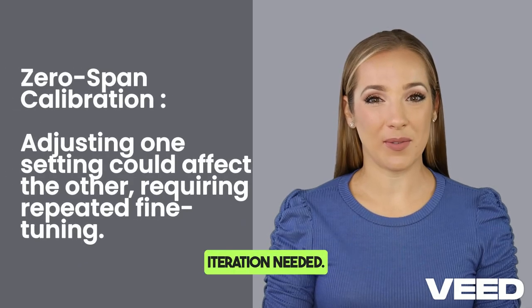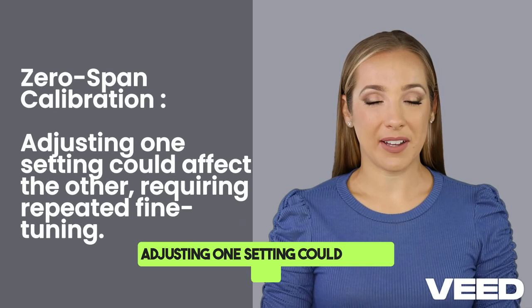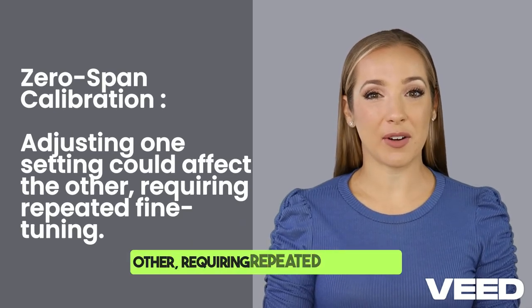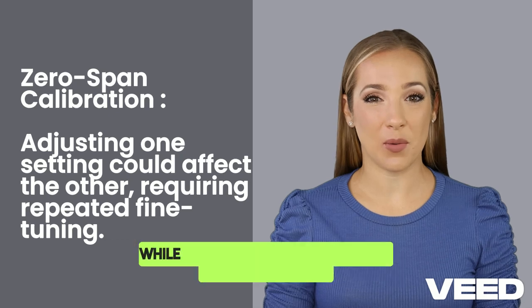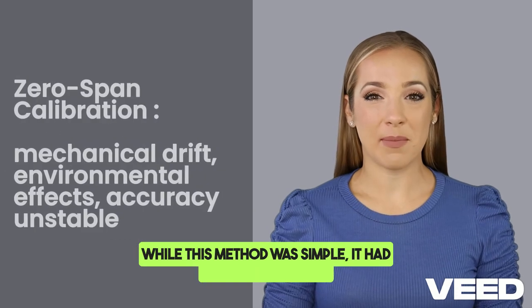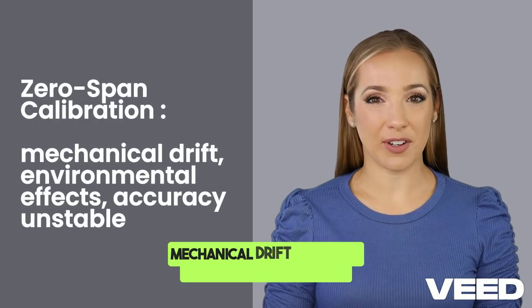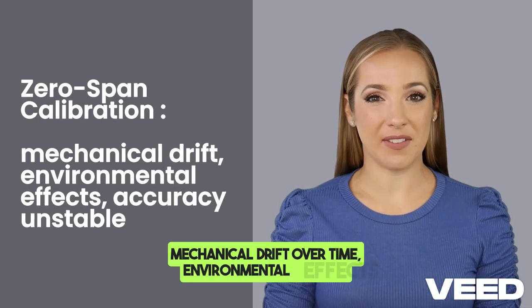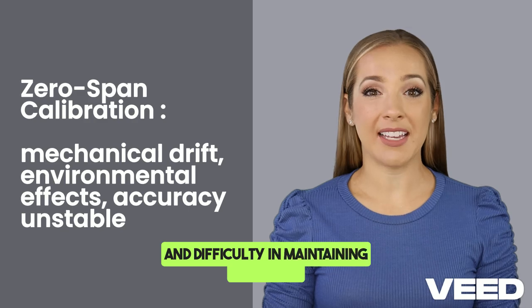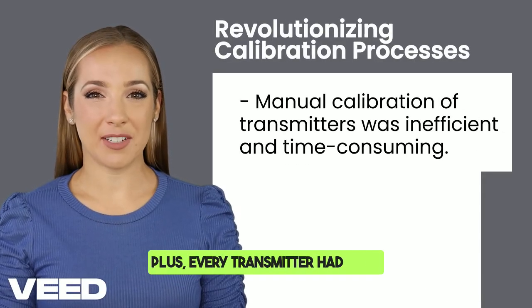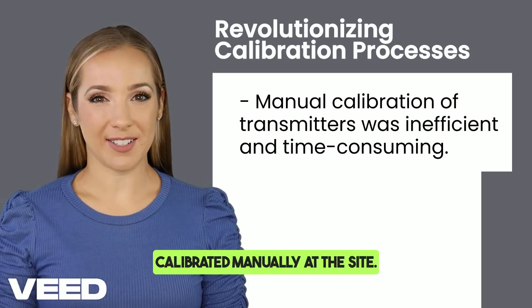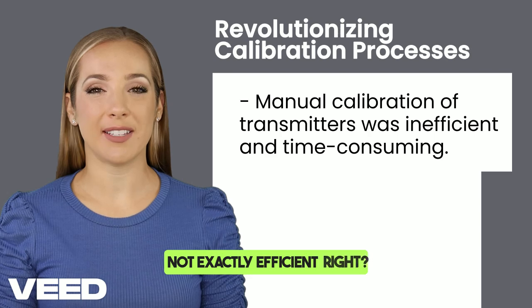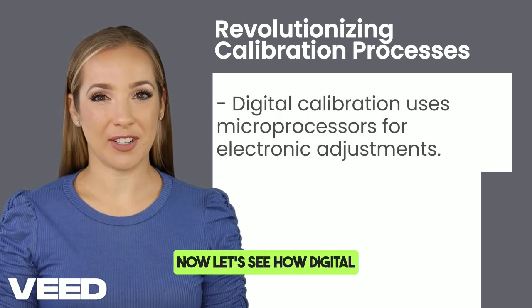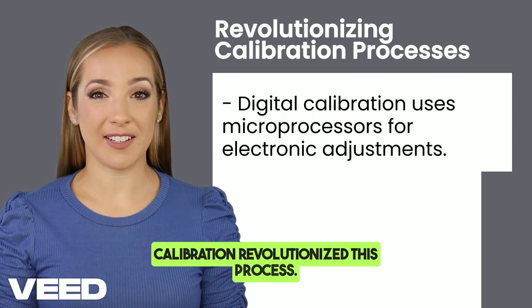Iteration needed. Adjusting one setting could affect the other, requiring repeated fine-tuning. While this method was simple, it had major drawbacks: mechanical drift over time, environmental effects, and difficulty in maintaining accuracy. Plus, every transmitter had to be calibrated manually at the site. Not exactly efficient, right? Now let's see how digital calibration revolutionized this process.